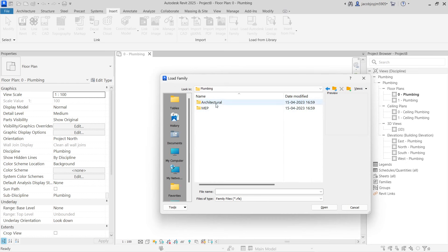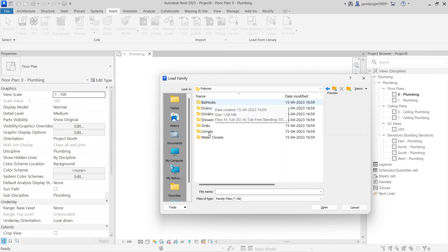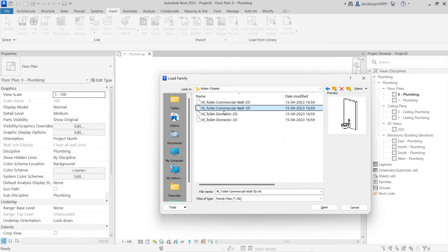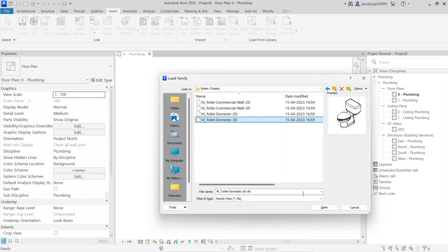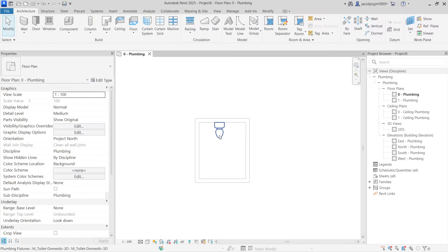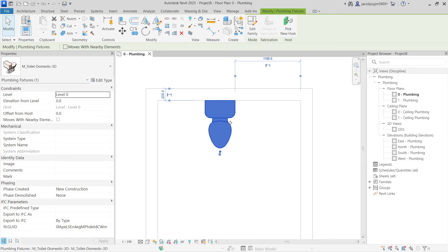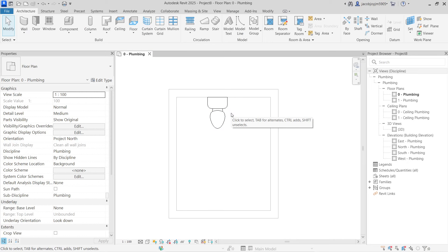In the Plumbing folder, there are two subfolders: Architecture and MEP. The Architecture folder contains fixtures like the water closet that architects use. When you place the architecture toilet family, it is just a 3D object — there is no pipe outlet or inlet. But when you are modeling for MEP or plumbing drainage, you have to use the MEP folder. I'll show you the difference.